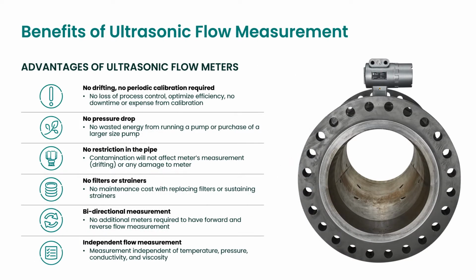Many people now choose ultrasonic flow meters due to their natural advantages. A common choice for selecting an ultrasonic flow meter is that these types of flow meters do not drift or require periodic maintenance. Ultrasonic flow meters have no moving parts or parts that could wear over time. Therefore, an ultrasonic flow meter is very repeatable over the life of the product for excellent process control optimization and efficiency. Also, no calibration or periodic maintenance is required once installed. Calibration and maintenance translate into both extra cost and extra time to maintain the meter.